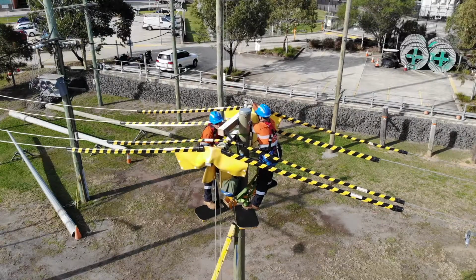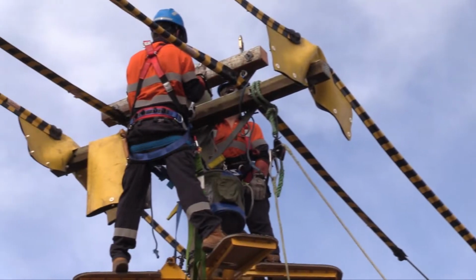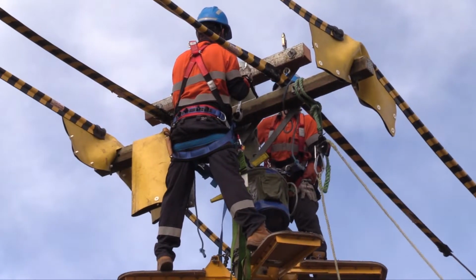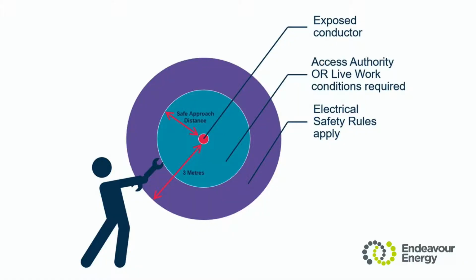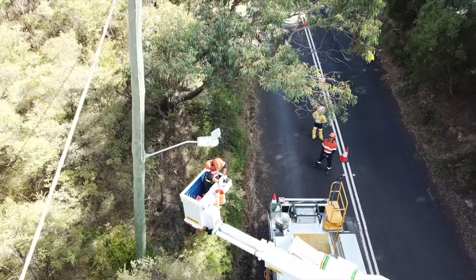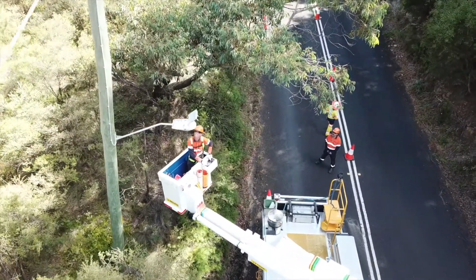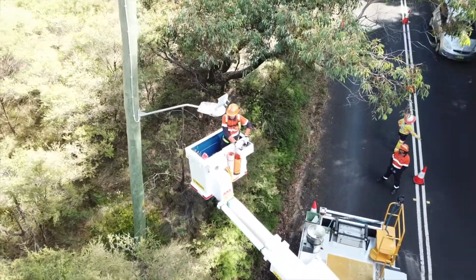Live work situations occur whenever we work within the safe approach distance of live low voltage exposed conductors, including touching the conductors. This is what we mean whenever we use the phrase "on or near." The control measures required for live work situations must be understood by all network workers because they apply whenever you are not working on isolated circuits.